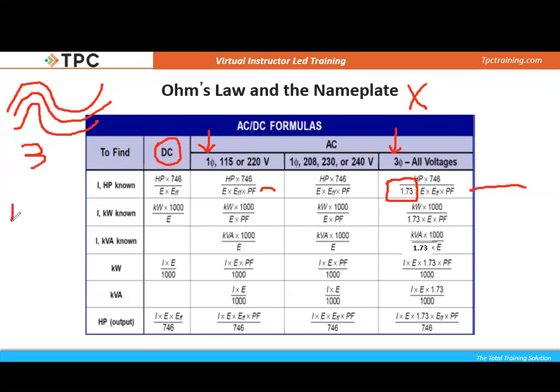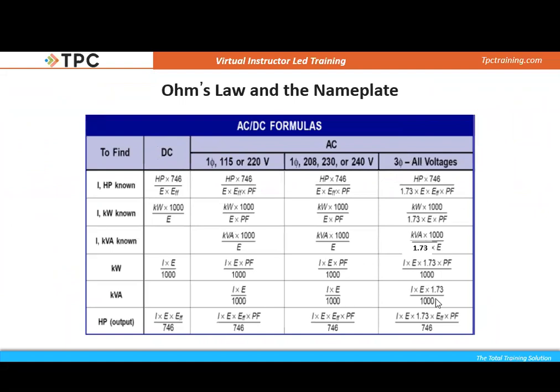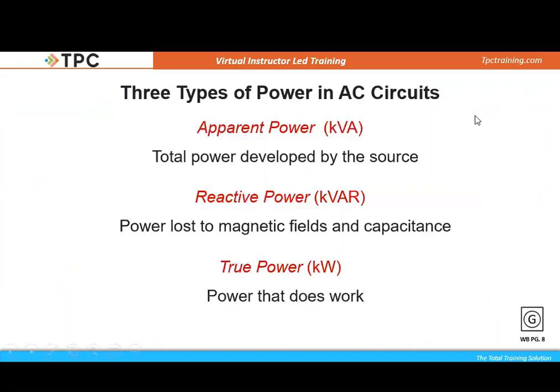But our three phases are separated by 120 degrees. And so now we have to use vectors to determine how much energy is going to be used. And those vectors are going to be separated, like I said, by 120 degrees. And when we do that, the square root of 3 comes into play. And for a long time, Nikola Tesla struggled with this, why he was only getting 1.73 times as much. But it's all because of the 120 degree separation that we have. So anytime we do a three phase calculation, we have to utilize 1.73, the square root of 3, plus the power factor. Okay, so you can see here three types of power in these AC circuits.